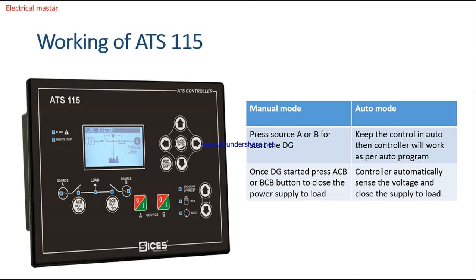Once it comes to the manual mode, for example, you connect source A for the transformer and source B for the generator. Now manually we want to start the generator. At that time you keep this LED in the manual mode and press this source B button, and it will give the command to start the generator. Once the generator starts, you can easily identify it on the display. See this, the dark block shows the generator has started, and it is showing the rated voltages here. Once the voltage is available, you just press this BCB breaker button, so it will close the generator breaker, and the generator supply will move to the load.